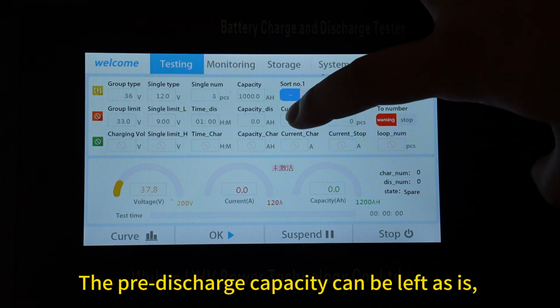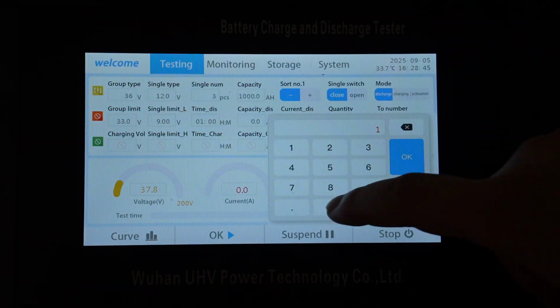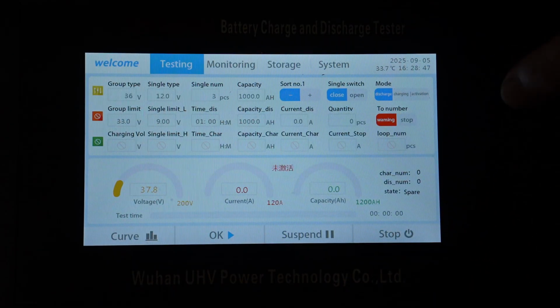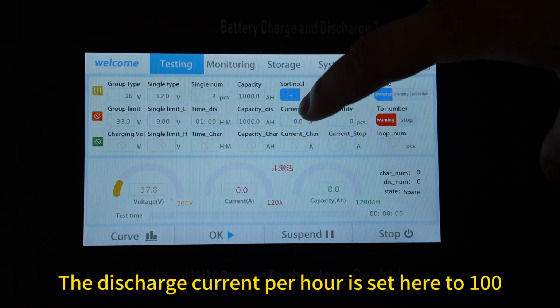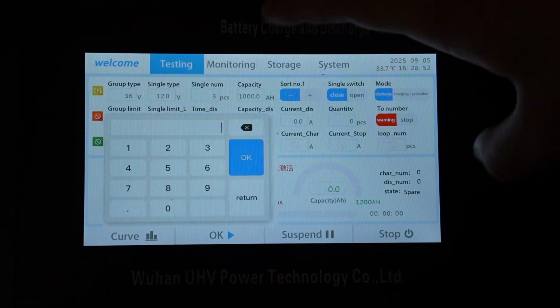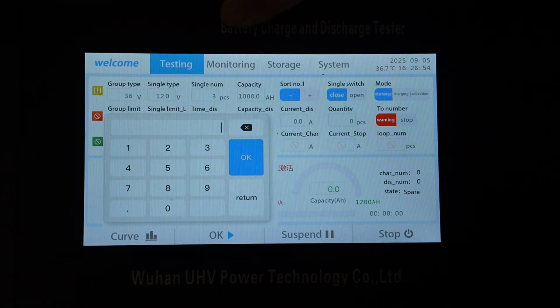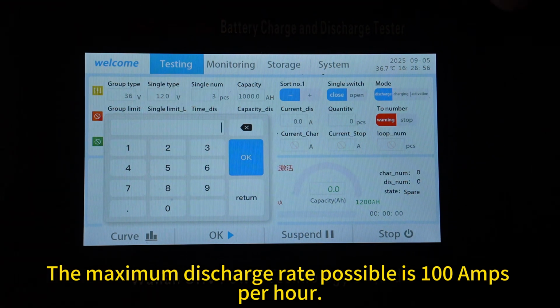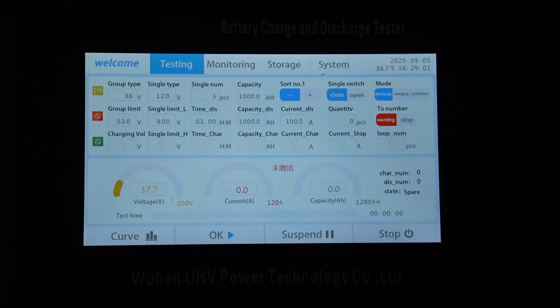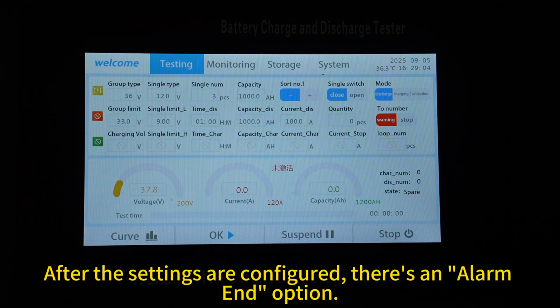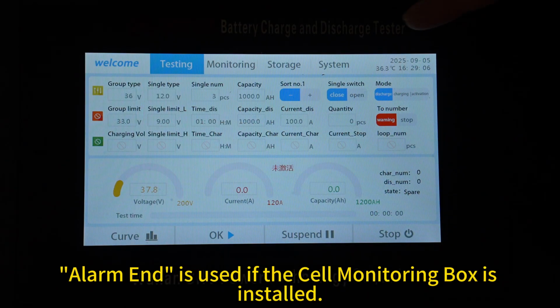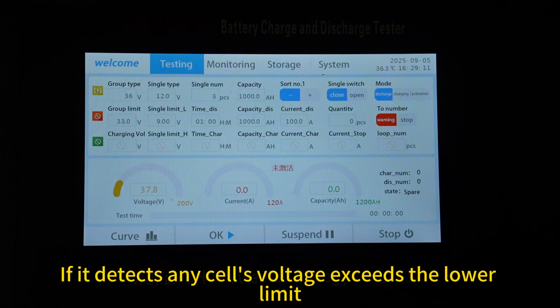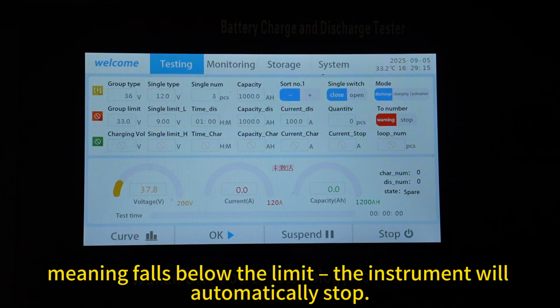The pre-discharge capacity can be left as is, or you can set a lower value. The discharge current per hour is set here to 100, meaning 100 amps. The maximum discharge rate possible is 100 amps per hour. After the settings are configured, there's an alarm end option. Alarm end is used if the cell monitoring box is installed. If it detects any cell's voltage exceeds the lower limit, meaning falls below the limit, the instrument will automatically stop.